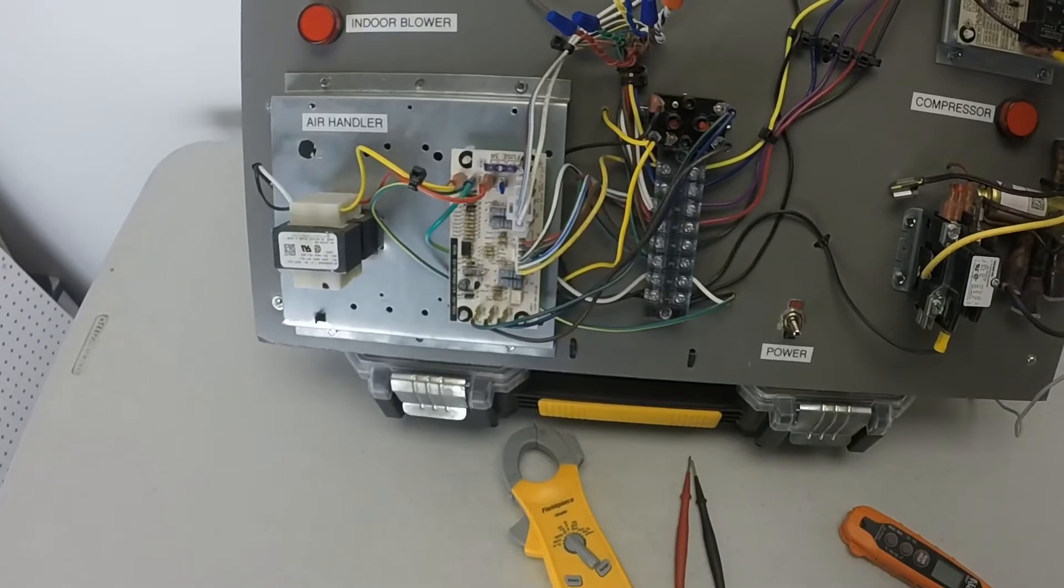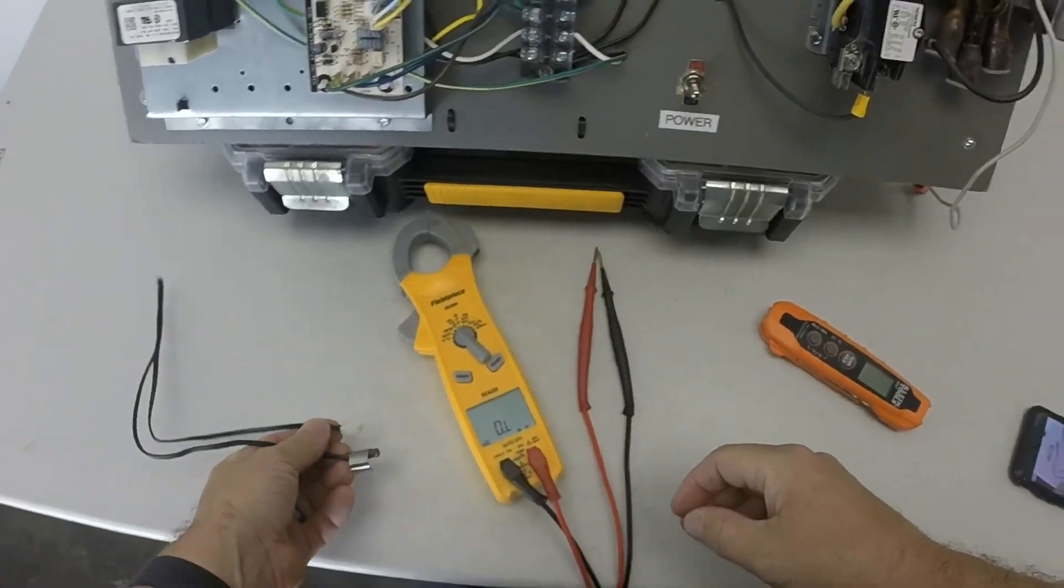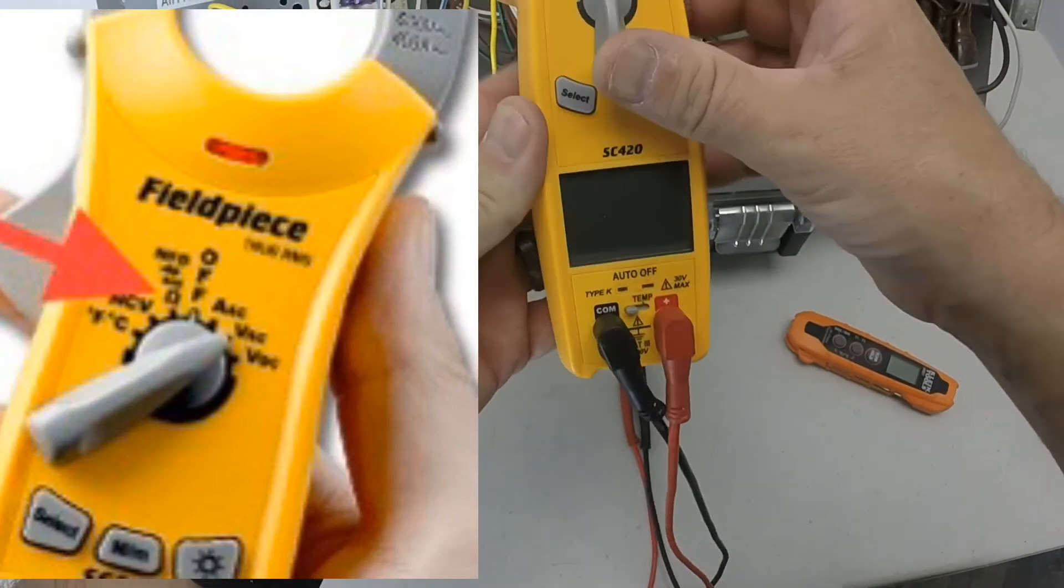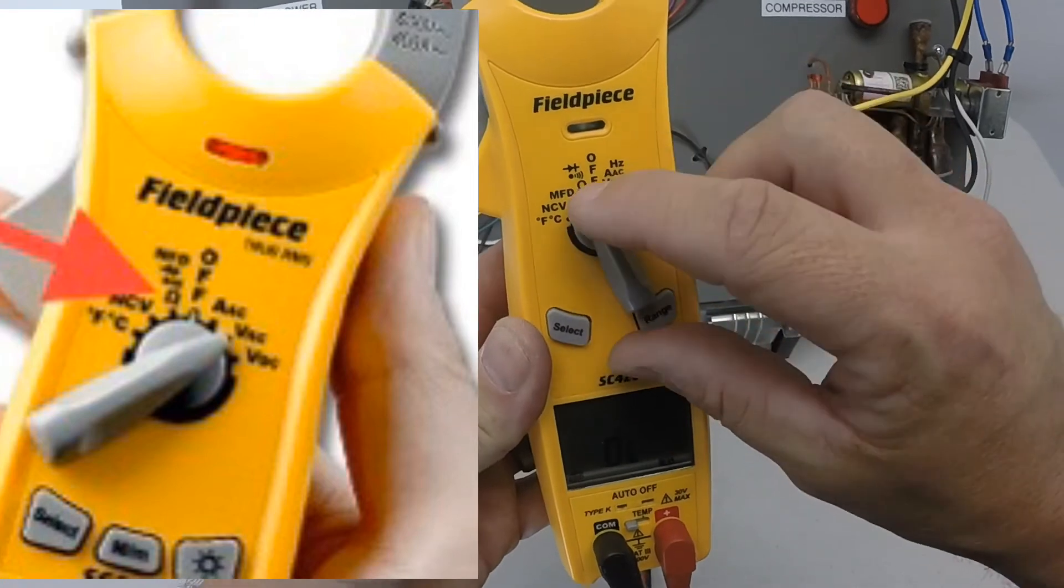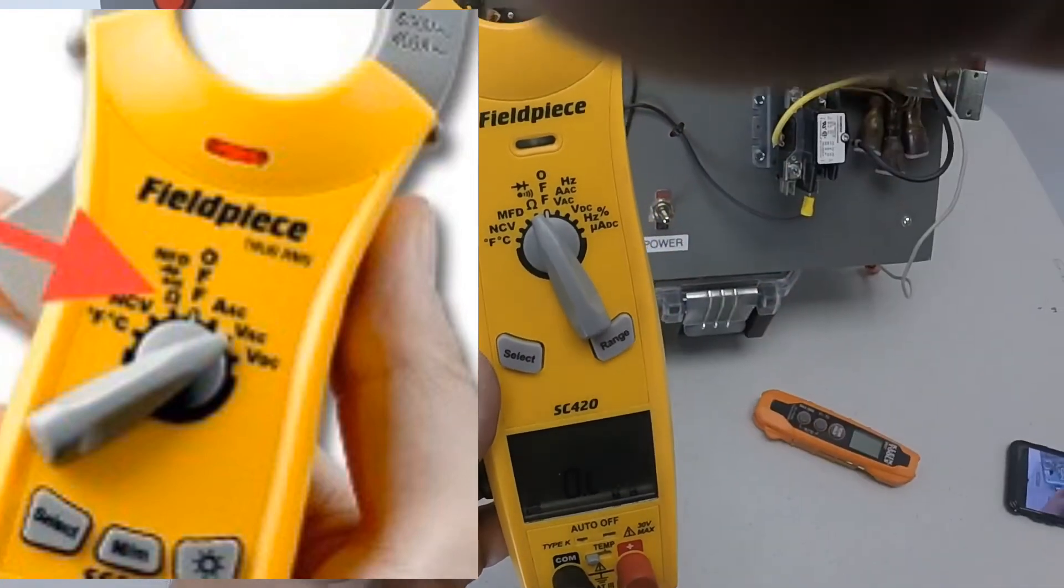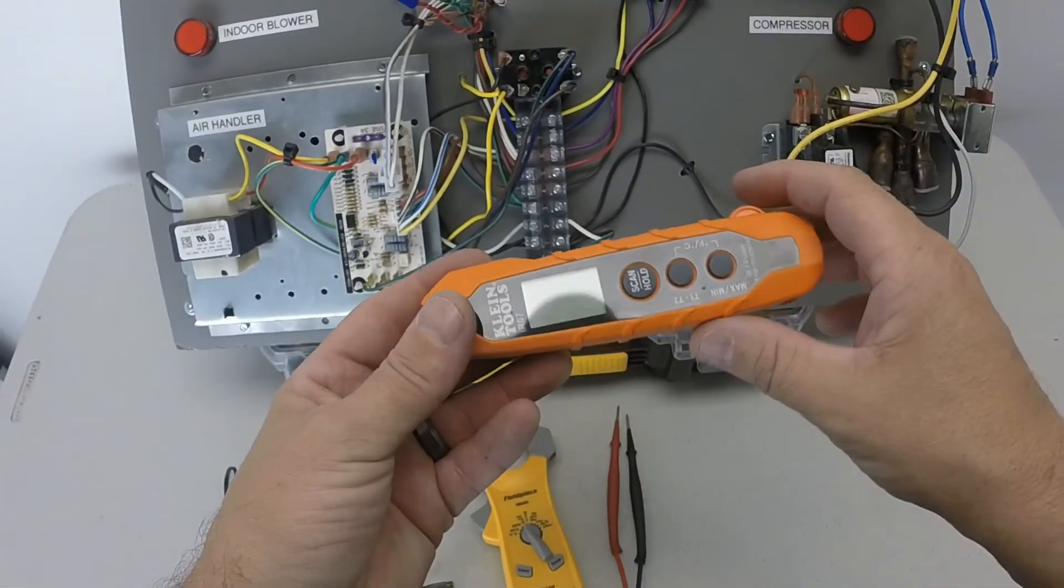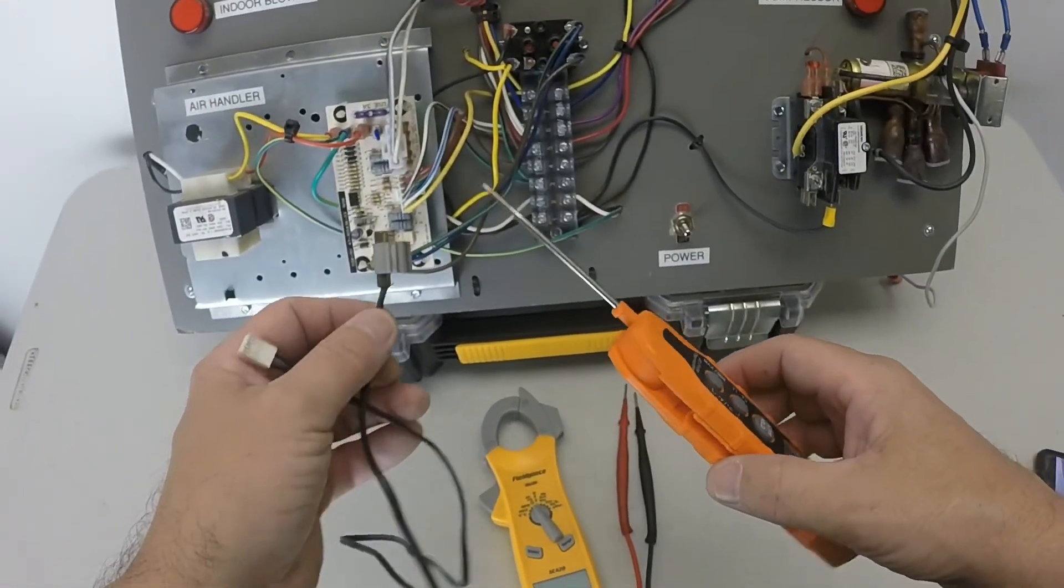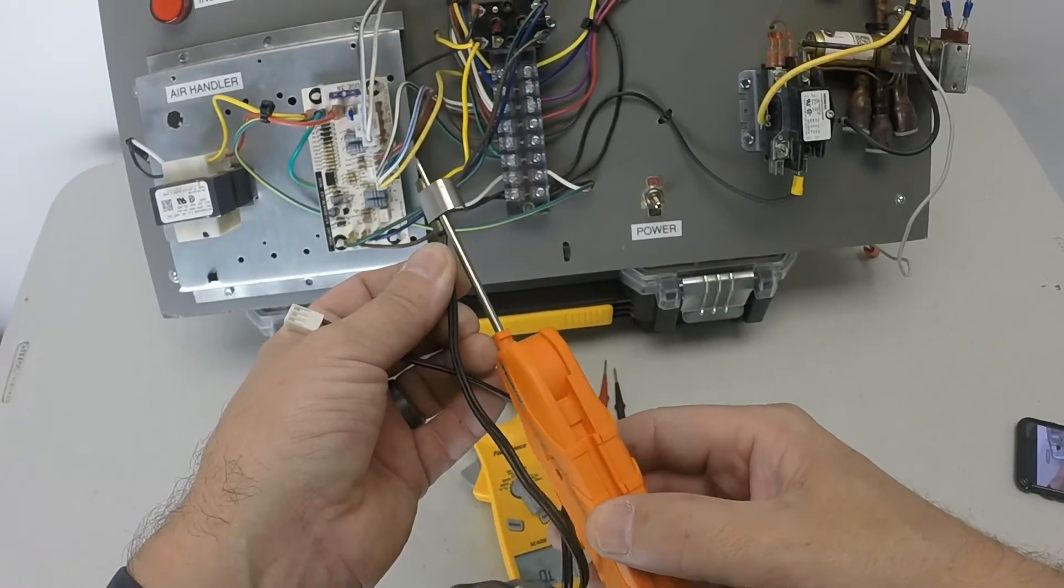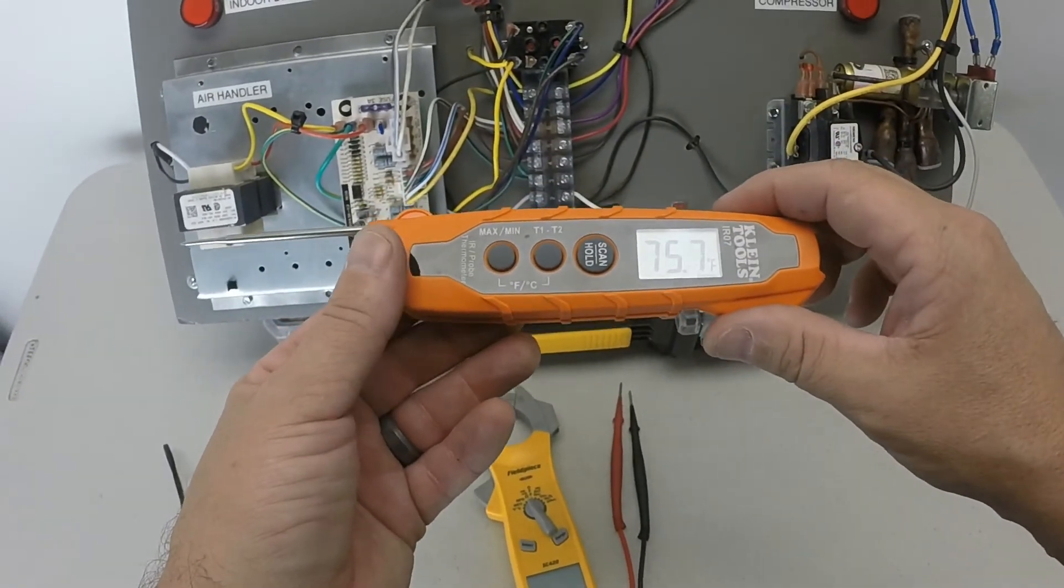Let's start with the coil sensor here. Got a couple basic tools here. We're going to need a multimeter here. We're going to put that on ohms. That's our horseshoe, kind of an upside down horseshoe there. All right, the other tool we're going to need. You need to know what temperature you're checking this thermistor at. A lot of guys like to strap this to do that, kind of let it sit a second, kind of see, you know, get a more accurate reading on what you're checking it against.